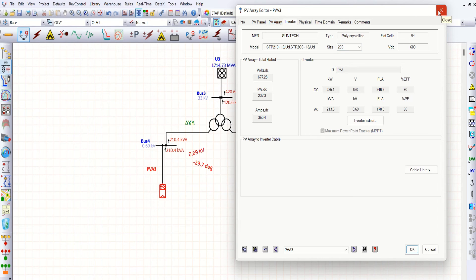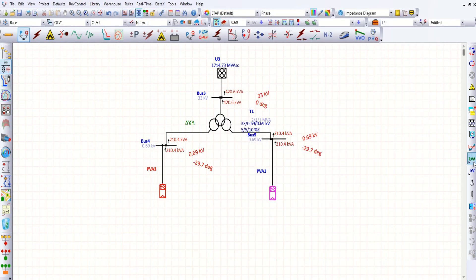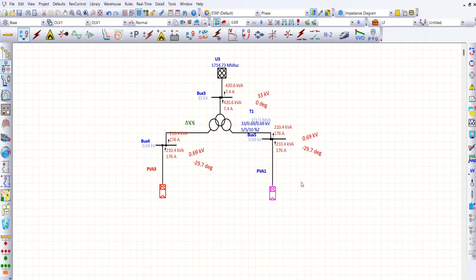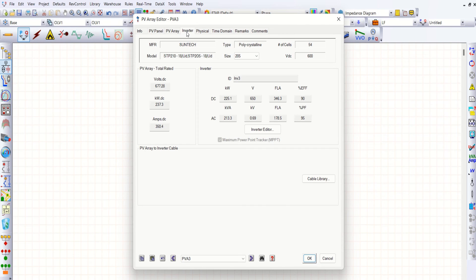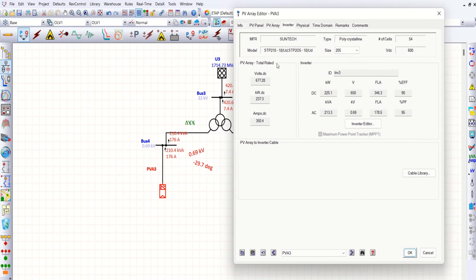What about the current? Let me check the current also. It shows 176 amps. Let me open one of the PV arrays and check — 176 amps here, approximately 178 amps. This is what is coming out of this PV array.